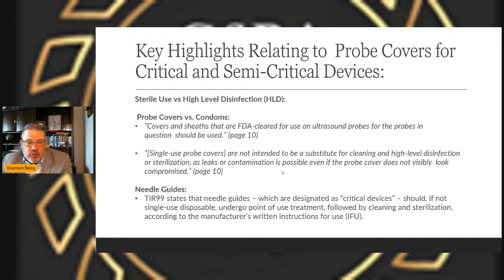There are also single-use probe covers that can easily do this, but they do not substitute for cleaning, and this is key. You still have to clean and disinfect it, because sometimes technique is maybe not the best, or they can puncture the sheath or the cover, and now you are still exposed. So you want to make sure you're still cleaning the best.